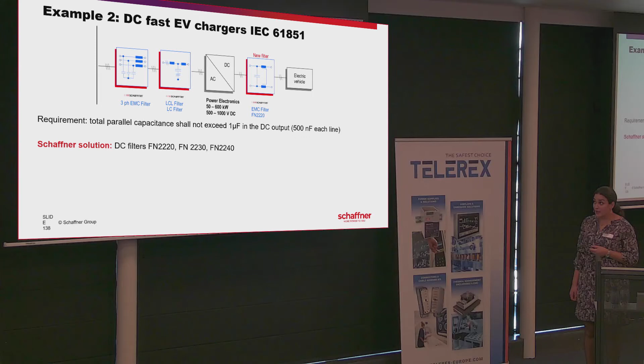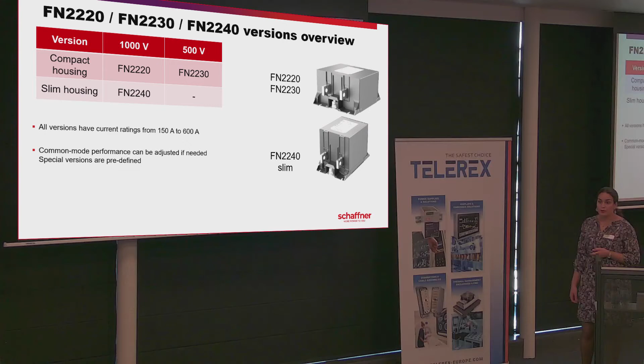and at this level we need to respect the requirement of 1 microfarad of common mode capacitors, which can be a bit limiting in terms of filtering. That's why we have developed these new filters, the FN2220, the FN2230, and the FN2240. So these filters can go from 150 amps up to 600 amps, and they are available both for either 1000 volts DC or 500 volts DC. And the advantage of this filter is that the common mode capacitors can be really adjusted according to the performance that is required. Well, that would be it for DC charging.